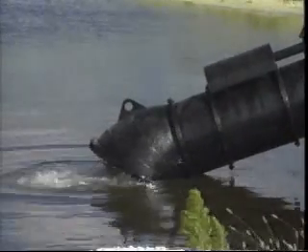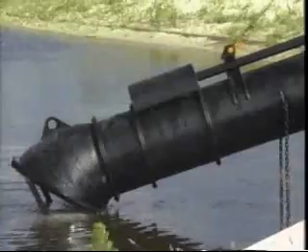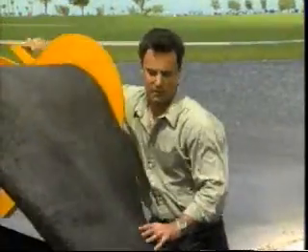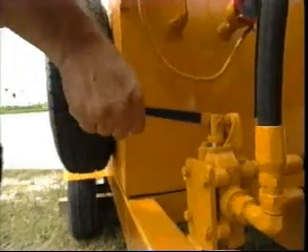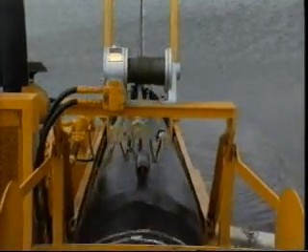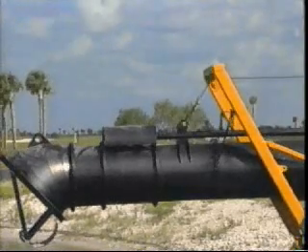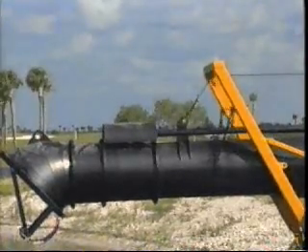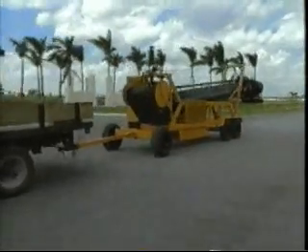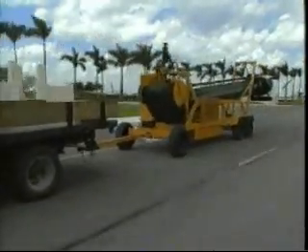Before the pump is fully raised, release the actuator lever in neutral position. This will help keep the pump suspended while the slack of the discharge hose is wound on the winch drum. Rebuild the pressure and raise the actuator to completely retract the pump. Be sure not to winch the cable clasp onto the pulley. Hook the safety chains and lower the pump until the weight is equally distributed between the chain and the cable. Relock the hose winch brake. Check safety devices and chains, and the MWI Mobile HydroFlow is ready to travel.